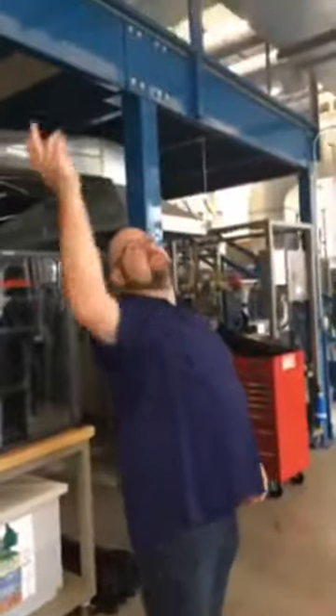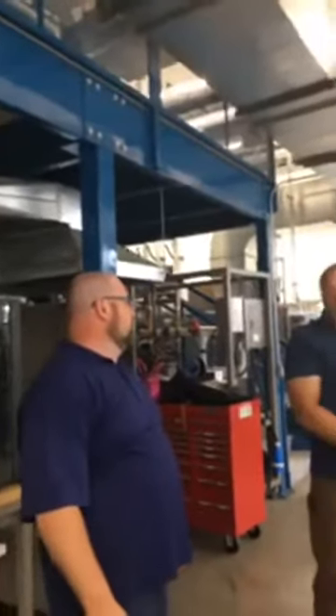Over here, a failed fire smoke damper, one that didn't get installed correctly, didn't get maintained, something of that nature. The smoke is continuing to make its way through. Right. So, we clearly have a definite difference between the two systems, and the importance of a fire smoke damper and its functionality is going to save lives, and that's the long and the short of it. Yeah, it really is.